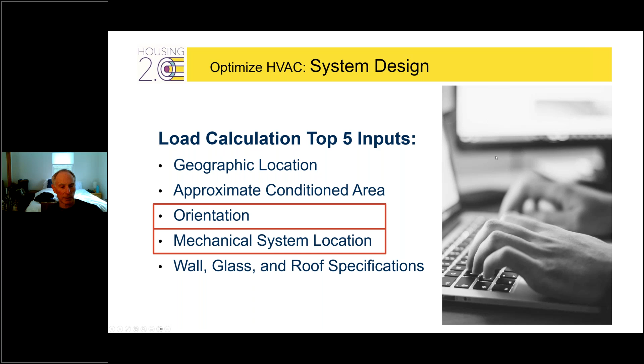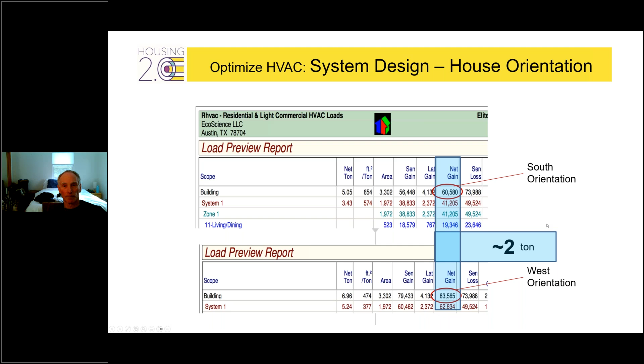Same thing with optimizing the enclosure—the walls, roofs, and glass—that will substantially reduce your heating and cooling system needs. But let's also talk about orientation and where we locate the heating and cooling system. Here are some engineering calculations looking at the same house, one with south orientation and one with west orientation. You go from 84,000 BTUs per hour to 60,000 BTUs per hour—pretty quickly a 2-ton savings on the system. That's substantial cost savings on both equipment and ducts, just from proper orientation.